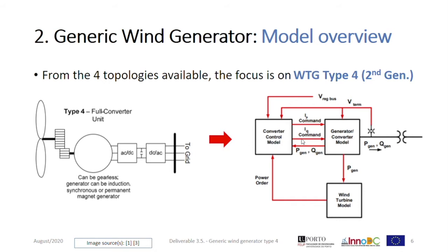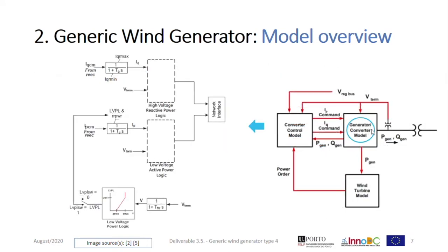The figure shows the components of the model. Here we have the generator converter model, and here the converter control model, and at the bottom the wind turbine model, with the connection point to the grid. The converter generator model receives its commands from the converter control model — specifically reactive and active power commands. These will go through high voltage reactive power logic, which provides reactive current to maintain the high voltage limit. Active current goes through a low voltage active power logic before interfacing with the network.